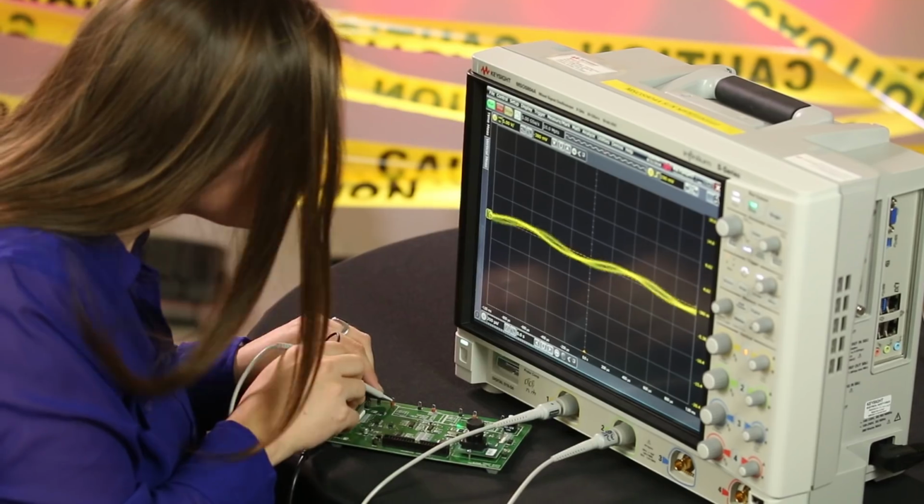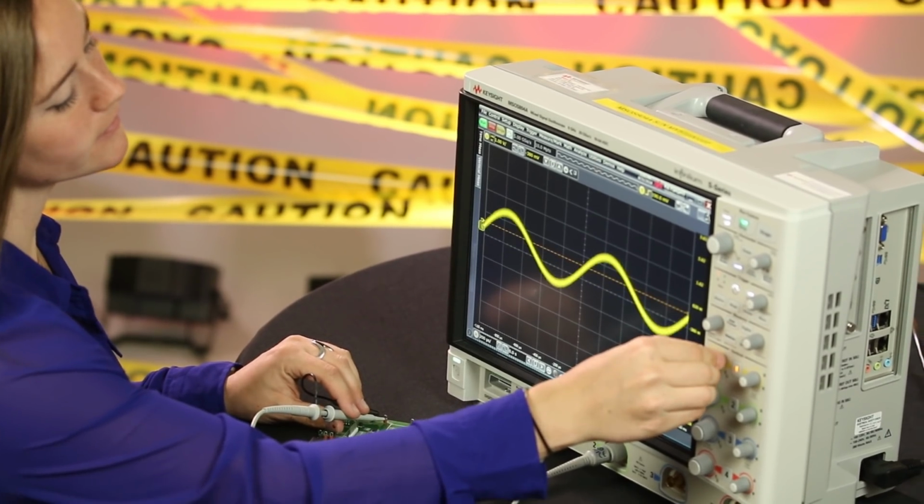The specification that you should really be looking for is the system's effective number of bits, or system ENOB. If you've never heard of system ENOB before, I'm not too surprised. The spec isn't talked about much, but I just said that it's the most important spec in determining measurement quality. In fact, it's what IEEE uses to measure an oscilloscope's signal integrity. So why isn't it talked about? System ENOB usually isn't mentioned because it's typically so poor. Also notice that I keep saying system ENOB, not just ENOB, and definitely not ADC ENOB.